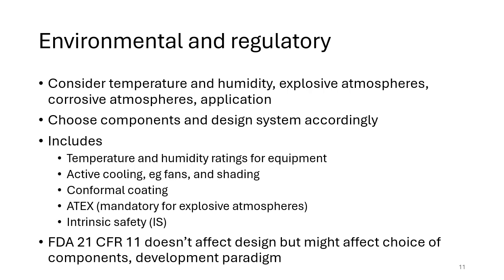FDA 21 CFR 11 is slightly different. This is often covering particular requirements for traceability and recordability. So that doesn't necessarily affect your design as much, but it might affect your choice of components, and it might affect how you develop the application, because you need to record everything you've done, and you also need, when the application is running, to record everything that the operators do as well. So these regulatory compliance requirements might also have an impact on the overall system, maybe at a higher level though than the particular component choice.